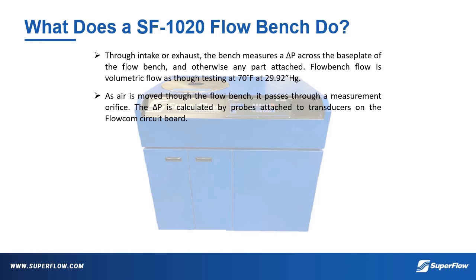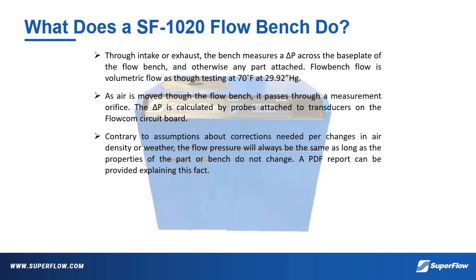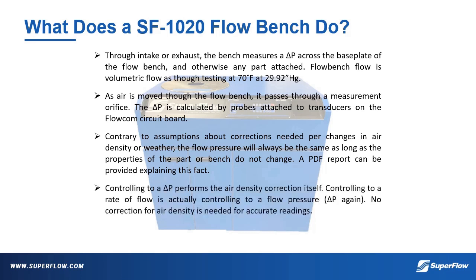The difference in pressure is calculated by probes attached to transducers on the FlowCom circuit board. Contrary to assumptions about corrections needed per changes in air density or weather, the flow pressure will always be the same as long as the properties of the part or bench do not change. A PDF report can be provided explaining this fact. Controlling to a difference in pressure performs the air density correction itself. Controlling to a rate of flow is actually controlling to a flow pressure. No correction for air density is needed for accurate readings.